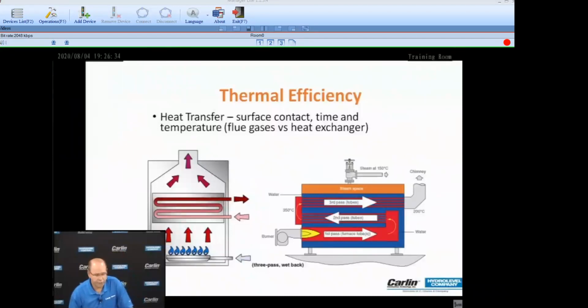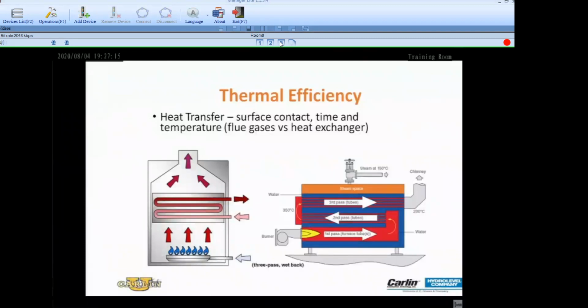Thermal efficiency, heat transfer on an appliance. It's important to note a single pass appliance, where the heat passes the heat exchanger one time on its way into the flue, as opposed to heat passing through the appliance several times. Here's a multi-pass boiler. That one happens to be steam. And we have a 3-pass wetback. This is more like a Scotch boiler type of setup. And it's much more efficient because we're extracting the heat out of the flue gases, since it has several passes over the heat exchanger.